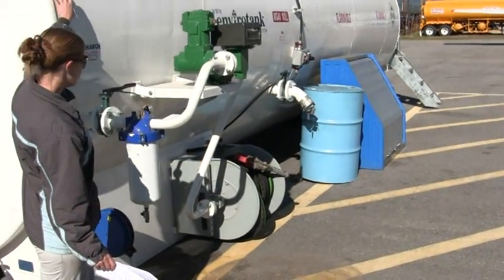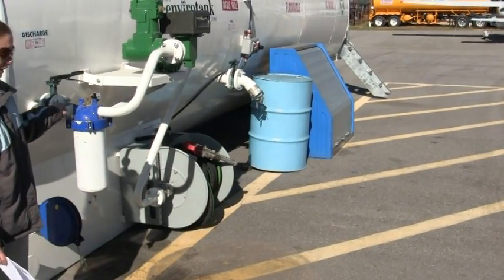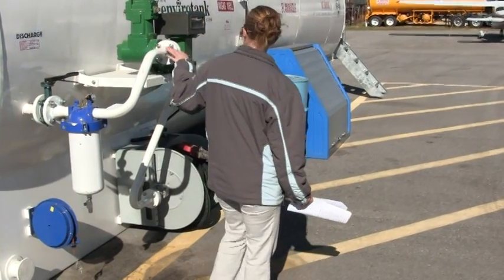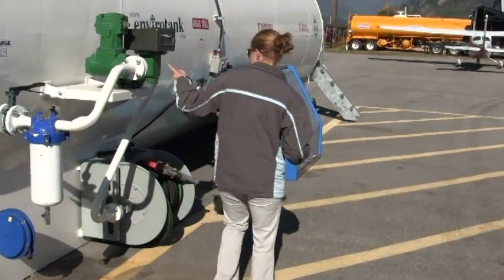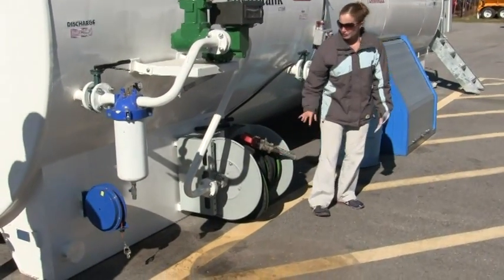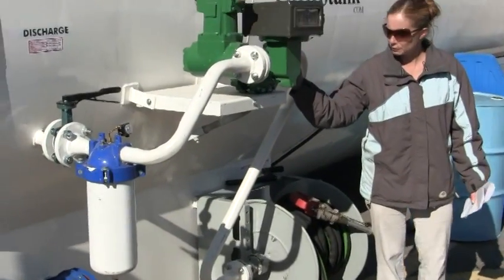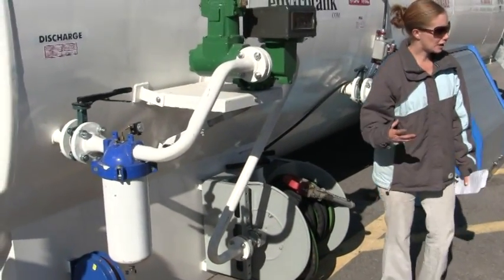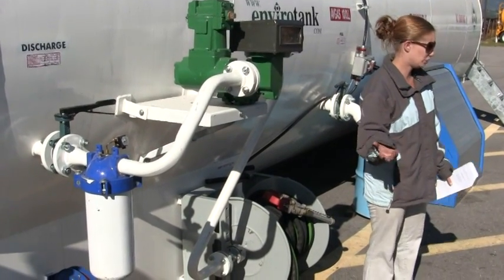So basically the fuel comes from within the tank. It comes out through this port here into this filter vessel where the fuel is filtered. It flows up and comes through the meter where the meter counts. Then it comes down this line through the nozzle. So if you guys are going to see any leaks, your probable points of leaks are going to be right here — anywhere where there's connections and even this valve down here. If you guys do notice any leaks, please let us know as soon as you can.